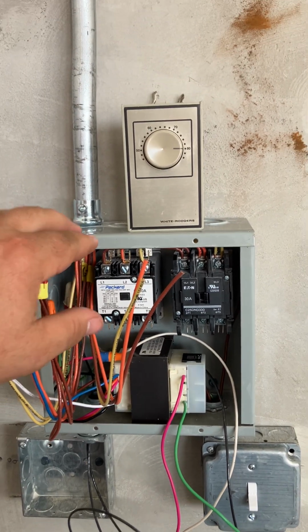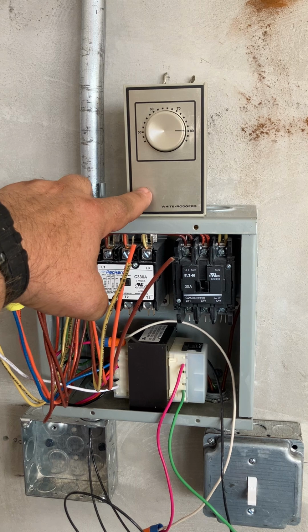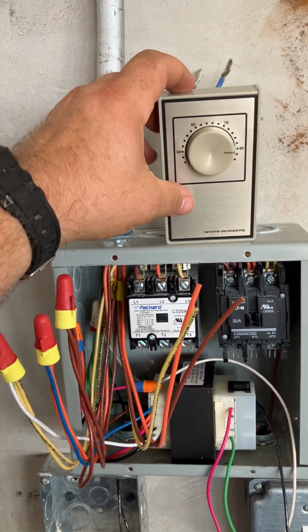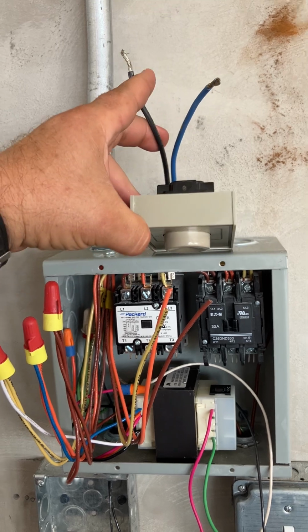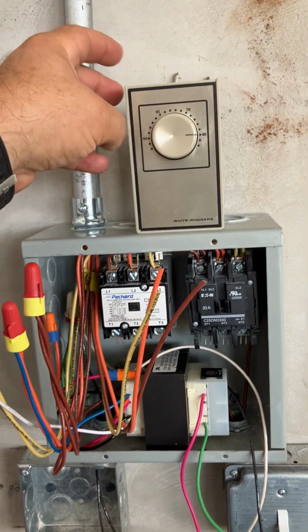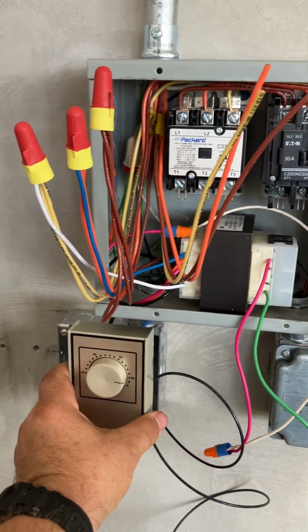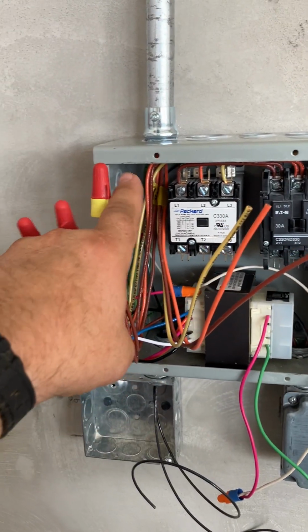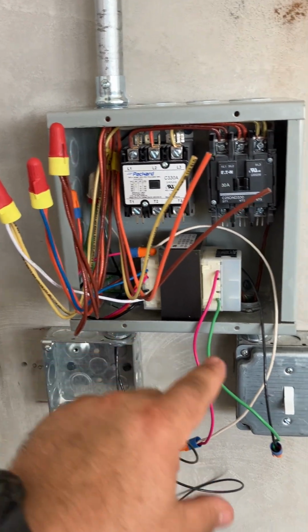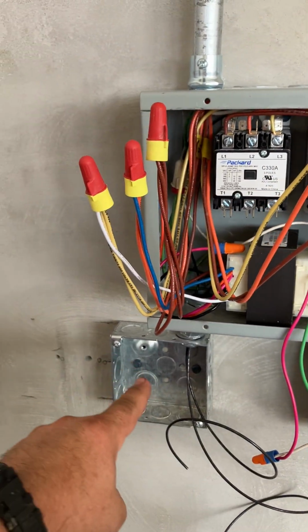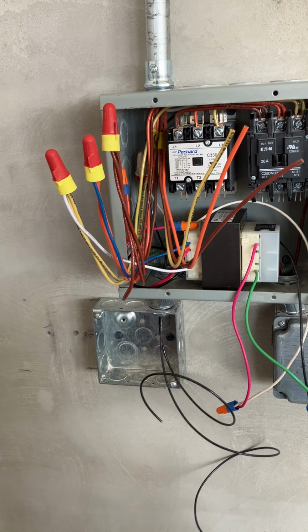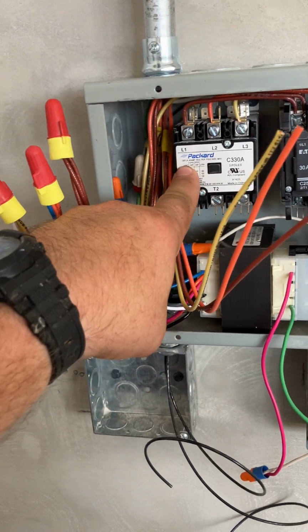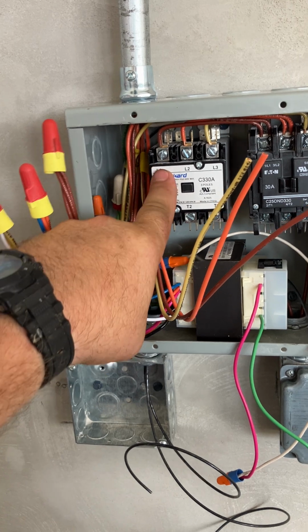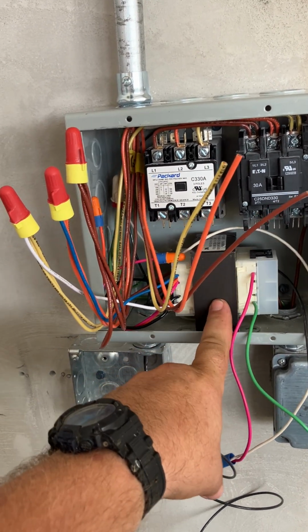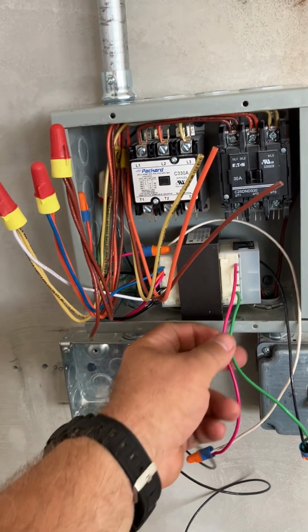But in the end, the HVAC guy never brought us anything but excuses, so I ended up having to dig through our warehouse and find this line voltage 277 volt thermostat, which I'm going to use here instead. And fortunately, when we pulled the circuit, we pulled a neutral, and so that neutral is going to help not only with the 277 volt switch, but now the line voltage 277 volt thermostat, which means that I no longer need this 3-pole 24 volt coil contactor, and I also no longer need this 480 single phase down to 24 volt transformer.